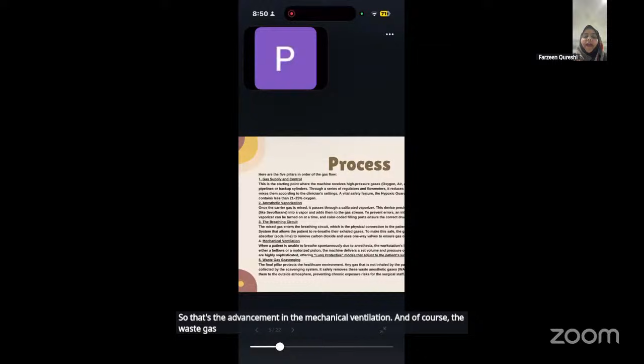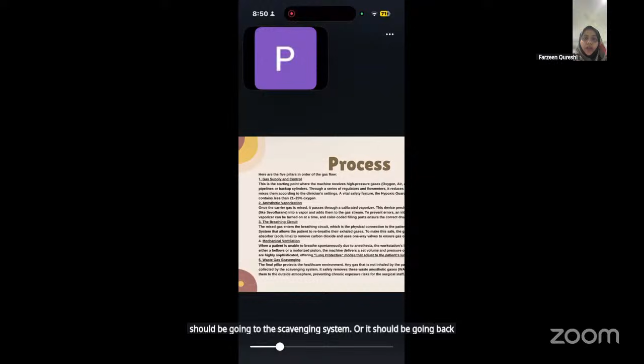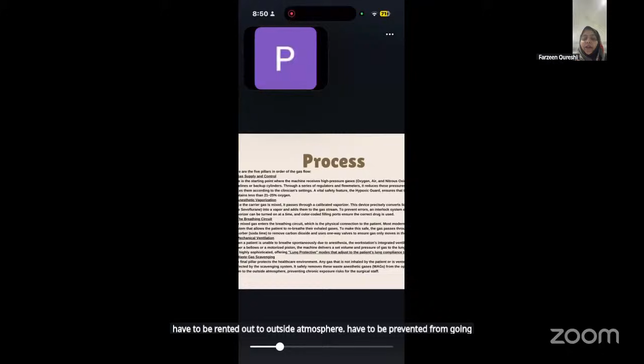And of course, the waste gas scavenging, this is the final pillar. This is for our protection. This is the protection of humanity and not just of the anesthetist. Any gas that is not inhaled by the patient should be going to the scavenging system, or it should be going back to the patient to get metabolized rather than polluting your OR environment. The waste anesthetic gases have to be vented out and prevented from going to the outside atmosphere, so that the chronic exposure risk and the greenhouse effect on the earth is prevented.